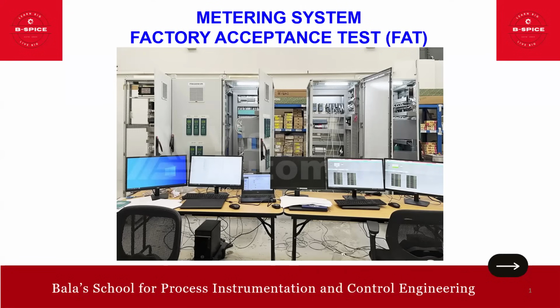Friends, prior to the FAT, the vendor shall issue the FAT procedure, isn't it? In that FAT procedure, they need to give the FAT schedule and the resourcing plan, and also arrange the availability of third-party subsystems at FAT where appropriate, and also the inventory and bill of material check, hardware testing procedure, software testing, including control loops, interlock, sequence, graphics, reports, and of course the integrated testing. All these we need to get. So assume that we got all this.